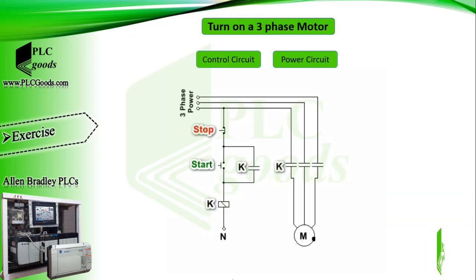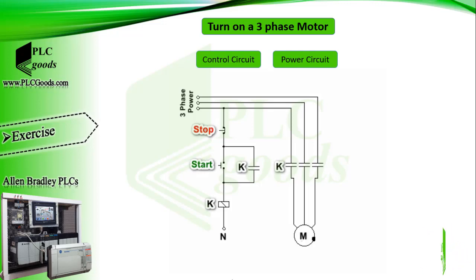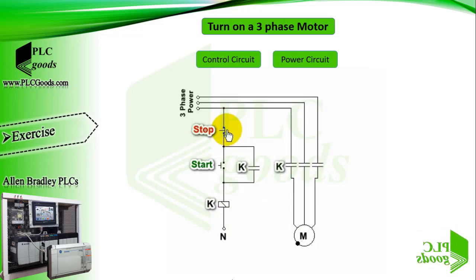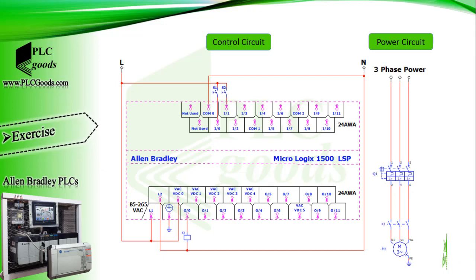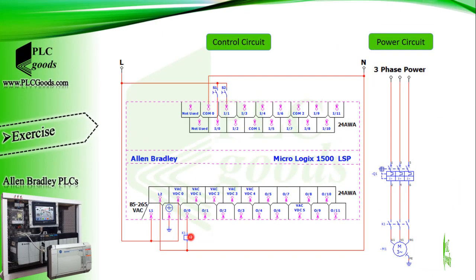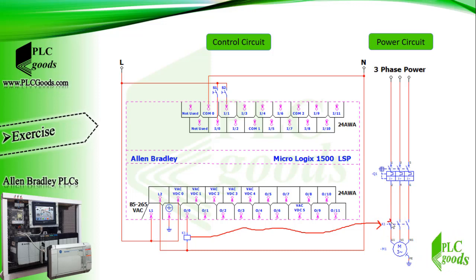Let's do a simple exercise. Here is a simple industrial circuit to turn a three-phase motor on and off. It can be divided into two parts: the control circuit and the power circuit. When the start push button is pressed, the K contactor is powered and closes its normally open contacts. The motor will remain on until the stop push button is pressed. PLCs can turn on small devices like signal lamps or contactors, but they don't have enough power to turn on three-phase motors directly, so a PLC must use a contactor whose contacts are used to turn on the three-phase motor in the power circuit.